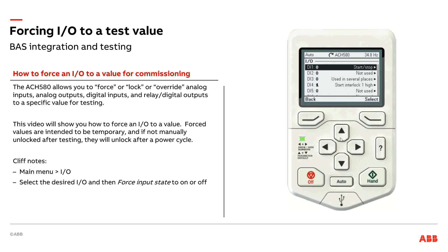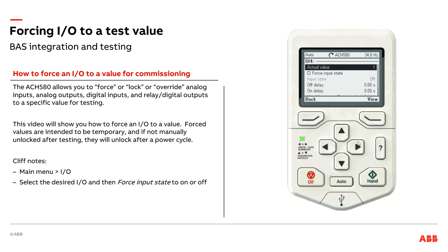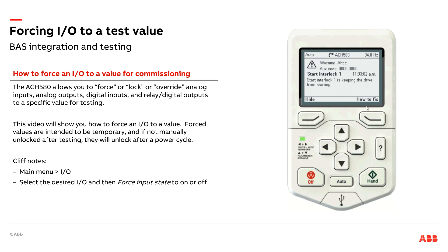Going back, let's look at digital input 4 — my safety. Let's say I wanted to simulate what happens if my safety were to open. Instead of taking the cover off, taking the wires out, or physically tripping a safety, I can simulate it here. I'll check this box and simulate it to be off. Immediately I get a 'start interlock 1' message letting me know that the safety is keeping the drive from being able to run. I'll go ahead and unselect that to release it back to its normal status.